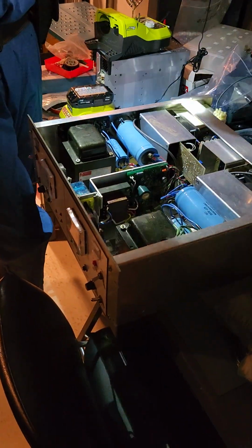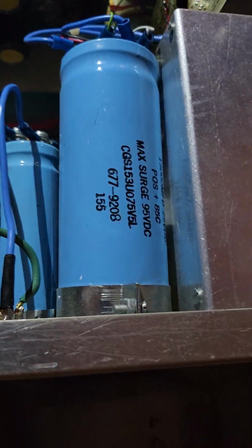The way that the PMTs work is that they have a photocathode on the front and then an electrical anode at the back. You hold this at a fairly high voltage potential. Nominally, these should have a 2000 volt potential across them. So your cathode will be at 0, the anode at 2000, or vice versa. But the way these work is that there are additional what we call dynode stages. There's a bunch of other plates inside of it that are all held at slightly different potentials.